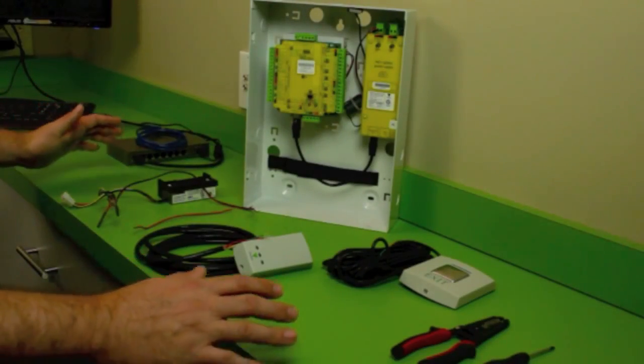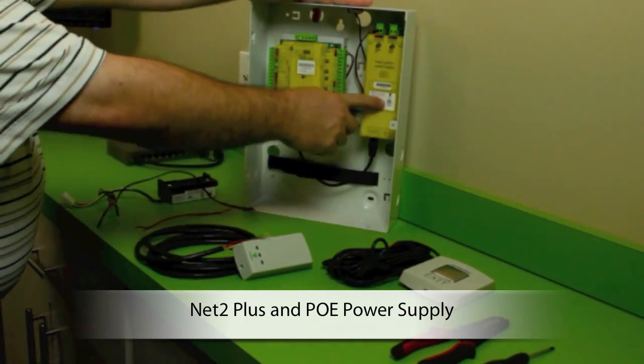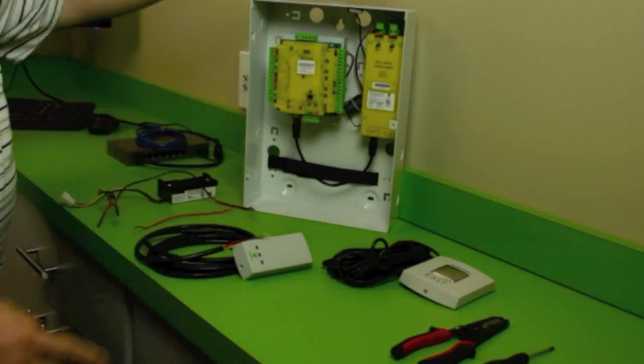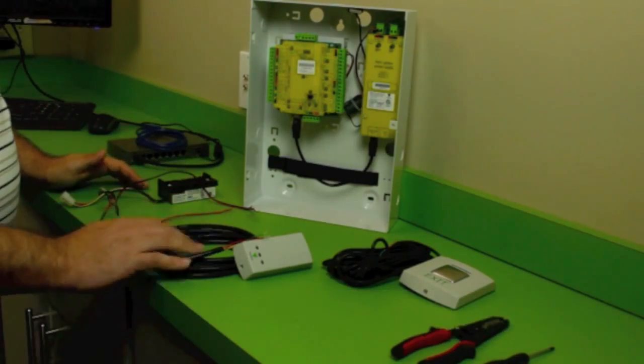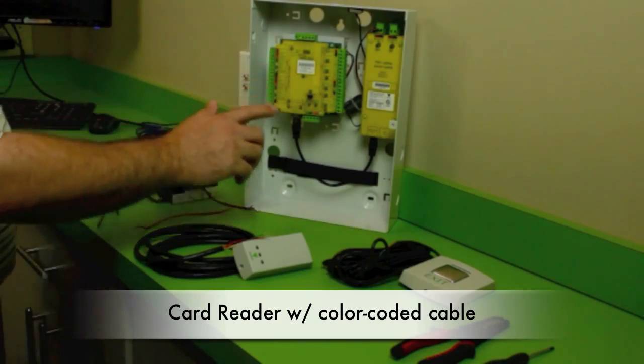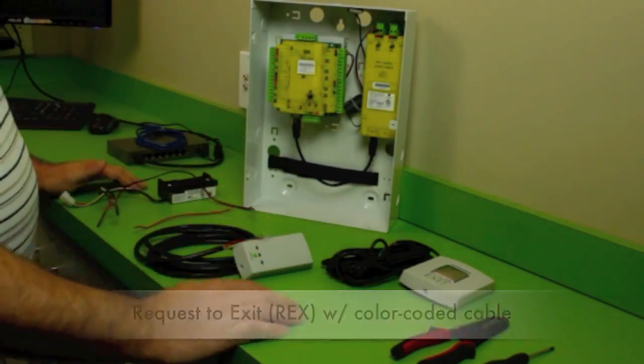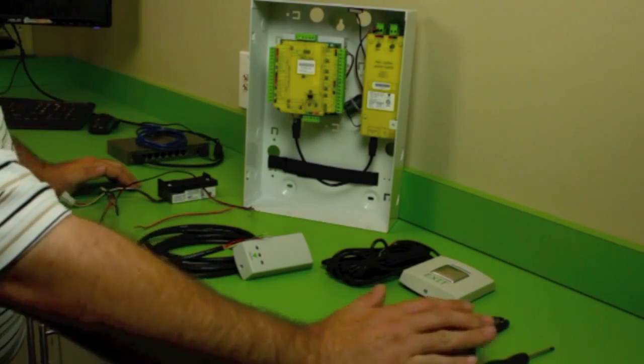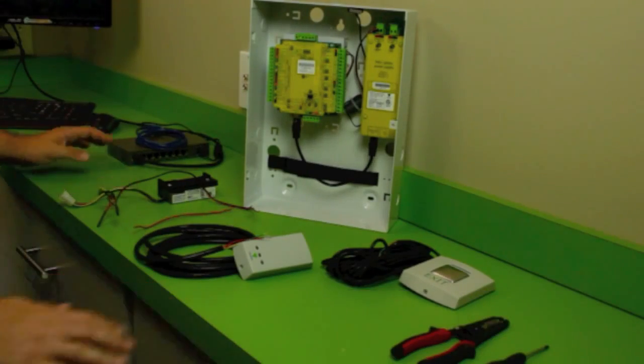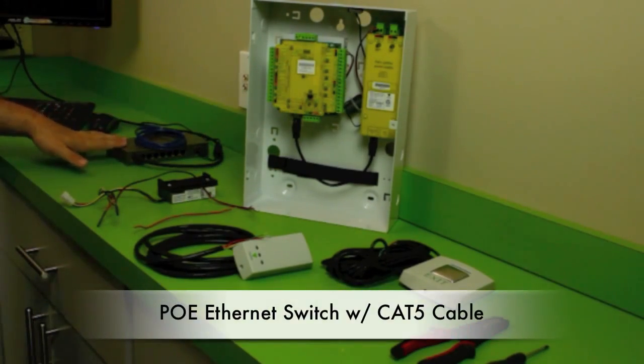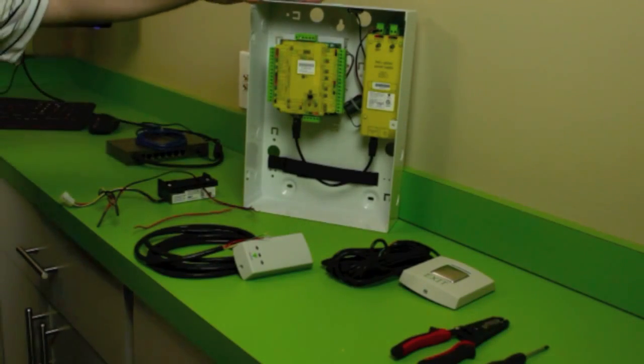So here are all the pieces that you need to get a door up and running. Main thing being your Net2 Plus board with your PoE power supply splitter. You have a strike with the wiring that would be coming from the door, your card reader that's color-coded to make it simple to wire into the Net2 Plus, as well as your push to exit button color-coded as well. You also only need a pair of wire strippers and a small flathead screwdriver to screw the wires into the controller. And lastly, you'll need a power over ethernet switch as well as a cable that would run from the switch to the controller.